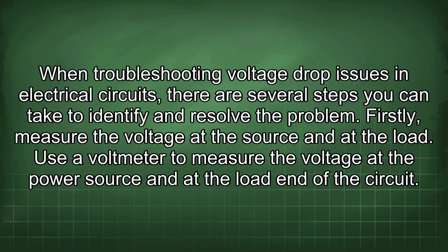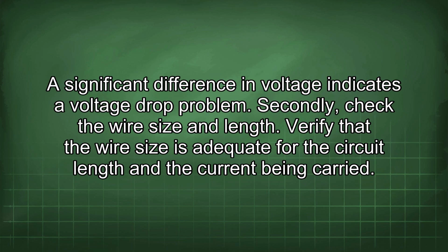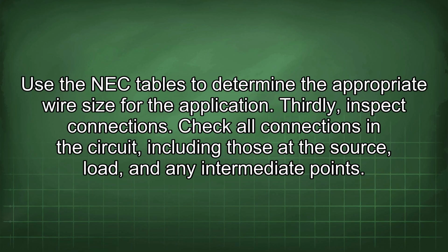When troubleshooting voltage drop issues in electrical circuits, there are several steps you can take to identify and resolve the problem. Firstly, measure the voltage at the source and at the load. Use a voltmeter to measure the voltage at the power source and at the load end of the circuit. A significant difference in voltage indicates a voltage drop problem. Secondly, check the wire size and length. Verify that the wire size is adequate for the circuit length and the current being carried. Use the NEC tables to determine the appropriate wire size for the application.